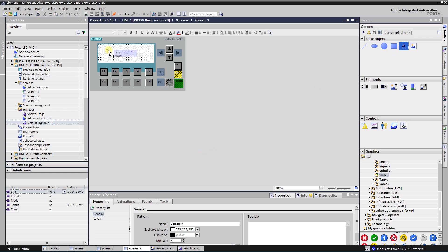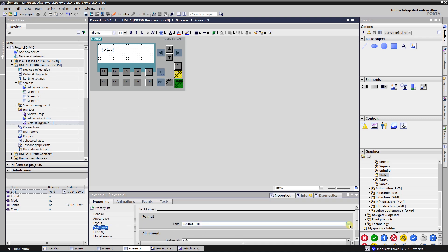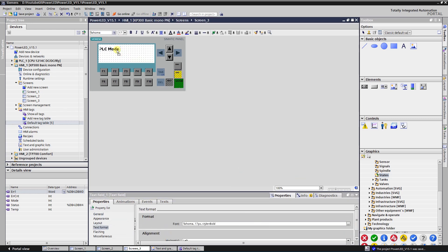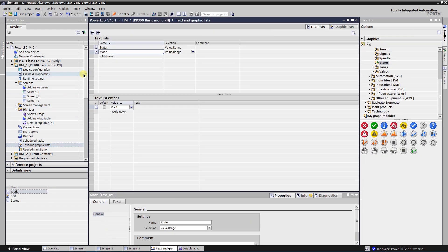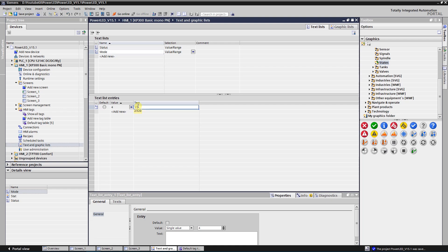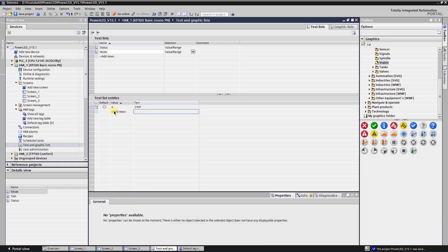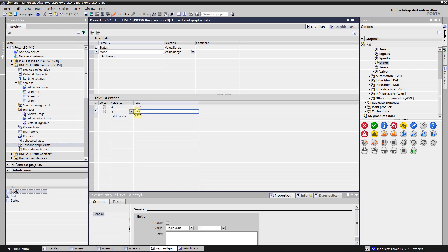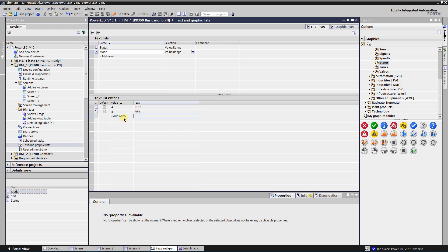Drag and drop a text field on it and write text PLC Mode, formatting the text as needed. Create a text list and name it Mode. Set two entries: first entry set value 4 and text Stop, second entry set value 8 and text Run. Create a tag where the function Get PLC Mode stores the current PLC mode — create an integer type tag, it will hold the value of the PLC mode.